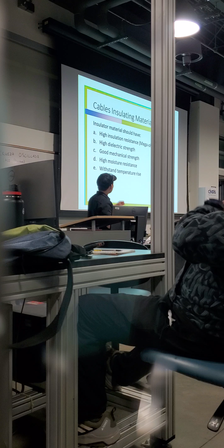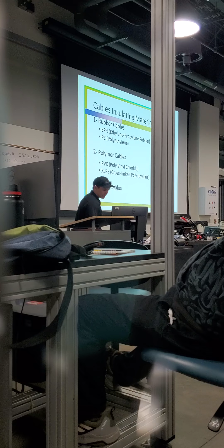And withstand temperature rise. A familiar analogy would be your 310.15(B)(2)(a), if I'm not mistaken, which would be your compensation factors for, like, elevated rooftop raceway in your NEC, right? To account for the undue heat that your conductors may face, because that's going to derate the allowable ampacity. So some kind of deal there.